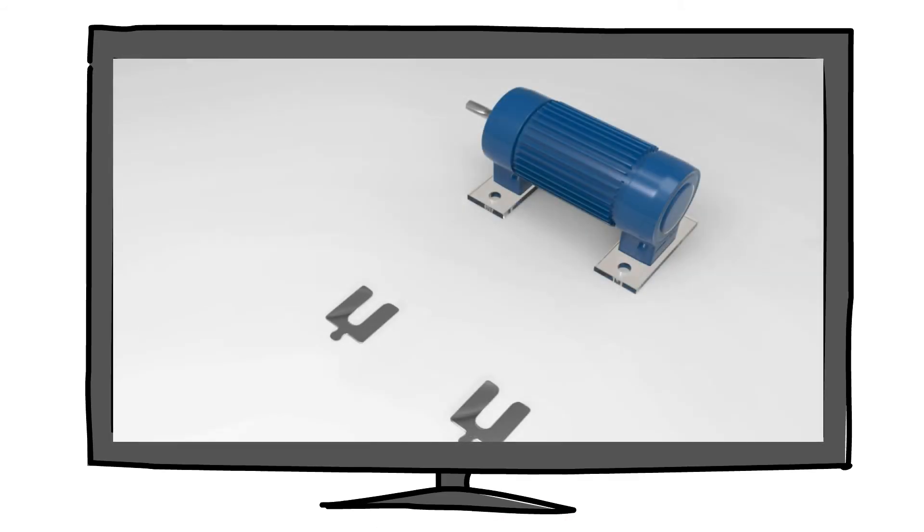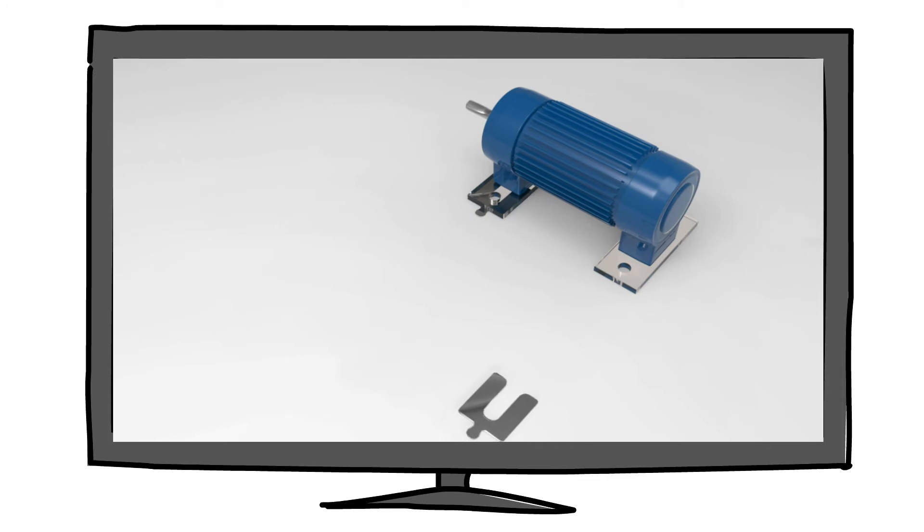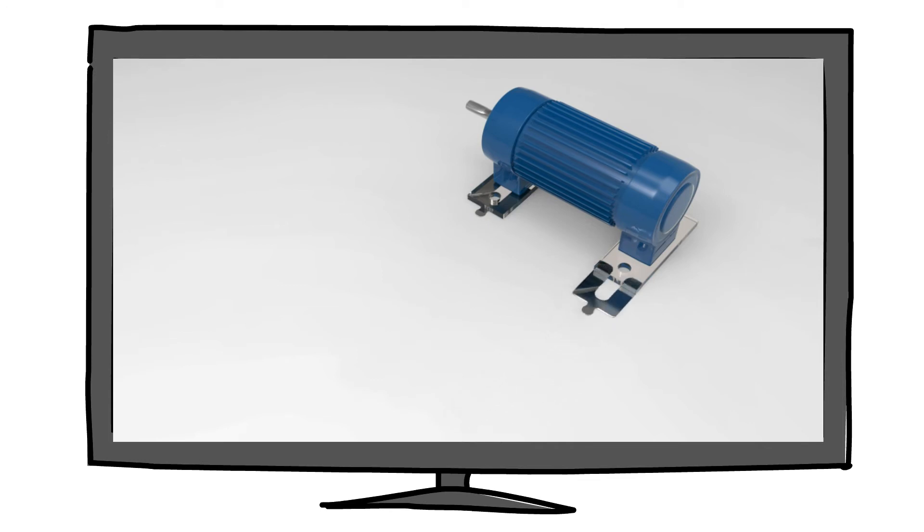Pre-cut shims are used to align pumps or machinery with more than one supporting base. The U-shape allows shims to be slotted seamlessly, from one end without the need to remove the entire base. Considering that most pumps and machinery are heavy, this makes alignment extremely convenient.